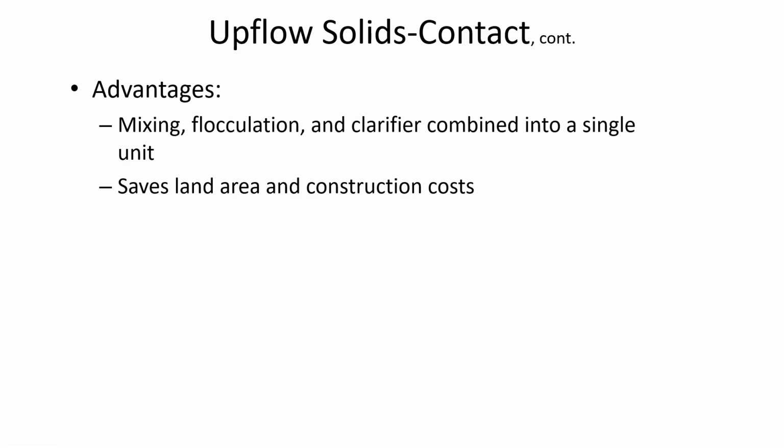So one topic that straddles both flocculation and softening is something called an upflow solids contact chamber. I'll show you a diagram of one in just a minute, but this is just a way of combining a clarifier, a mixing basin, and a place for flocculation to occur in a single footprint.